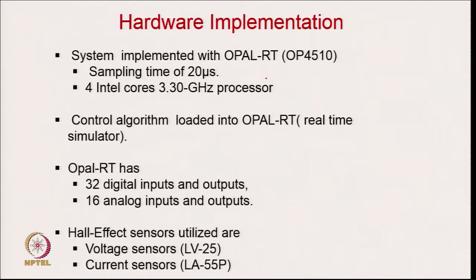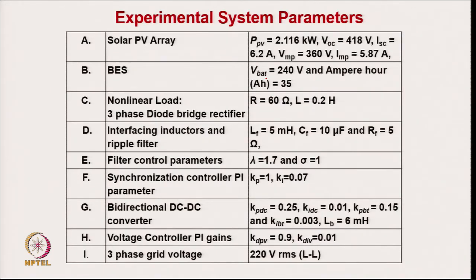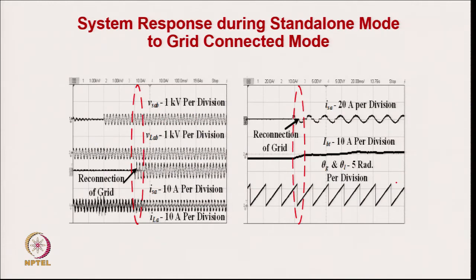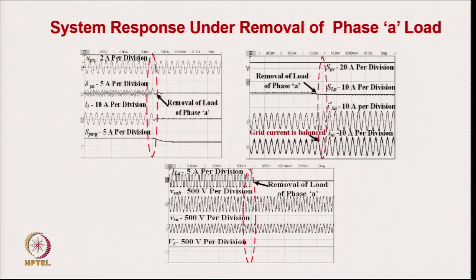For hardware implementation, an OPAL-RT processor is used for implementing the control algorithm with current sensors and voltage sensors in the practical system. In the experimental results, when grid is connected the system operates in current control mode showing grid voltage, grid current, and load current. When grid disappears, load voltage and load current are not disturbed. When the grid reappears, the system synchronizes and closes the switch — grid current starts appearing and the angle gets synchronized. Dynamics correspond to removal of one load phase: reference and actual grid current remain sinusoidal and balanced.